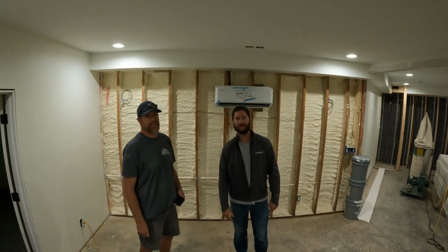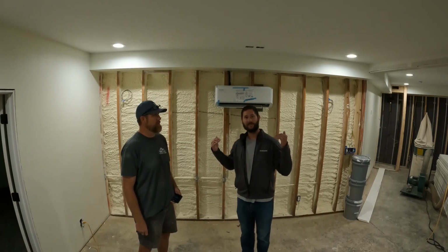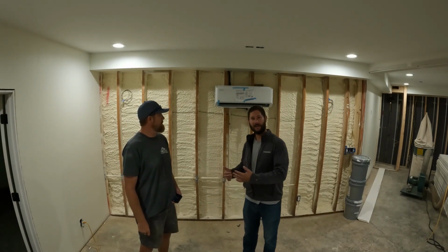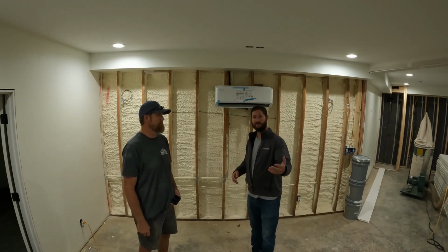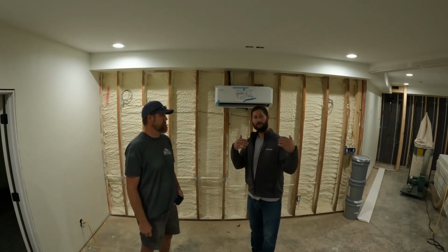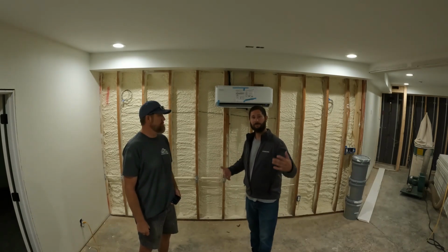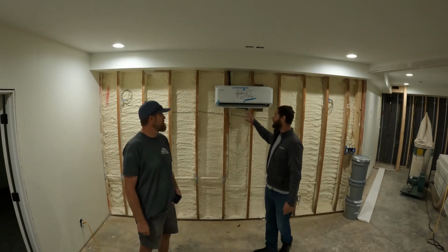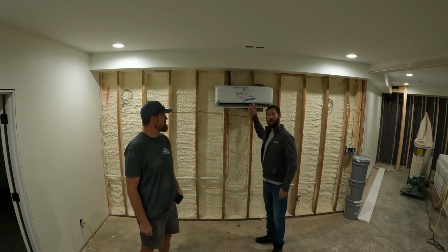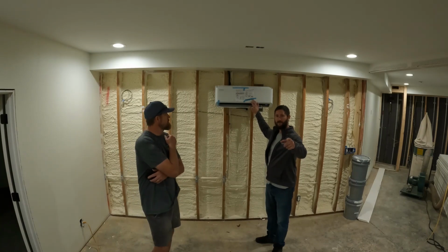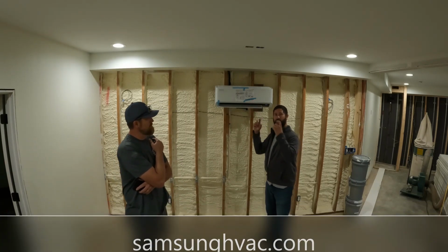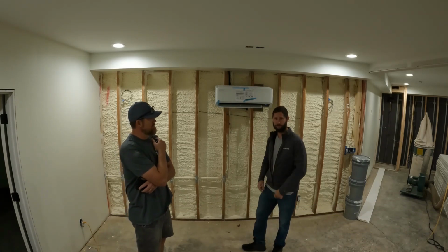So typically I use a square foot per ton sizing. When I size for homes, it's usually 500 to 600 square foot per ton. For standard insulation, for foam, it's about 1,000 square foot per ton. But something I do for mini splits is I go on a website, HVAC Downloads, SamsungHVACDownloads.com, and I look at their technical documents and actually look at the temperature and airflow distribution charts.